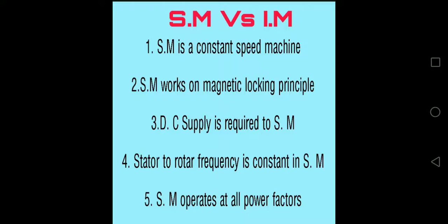A DC supply is required for the synchronous machine. A constant DC supply is required as the synchronous machine rotor supply. And coming to the fourth point, the stator to rotor frequency is constant in the synchronous machine. But in the induction machine, the stator to rotor frequency is not constant. The rotor frequency is very low and the stator frequency is equal to the supply frequency.